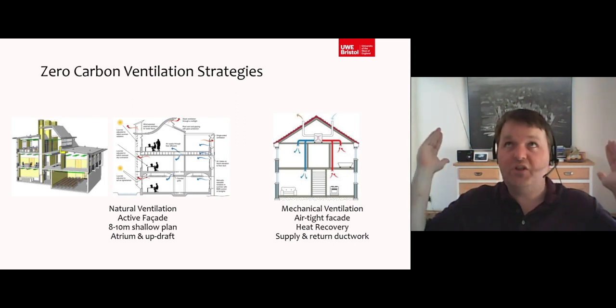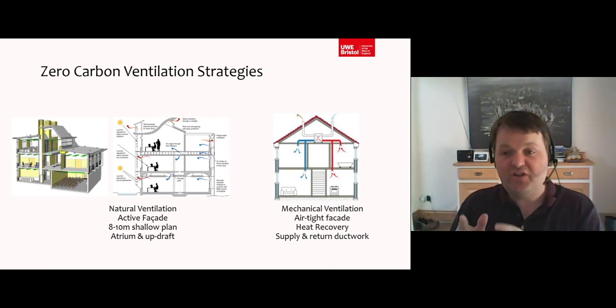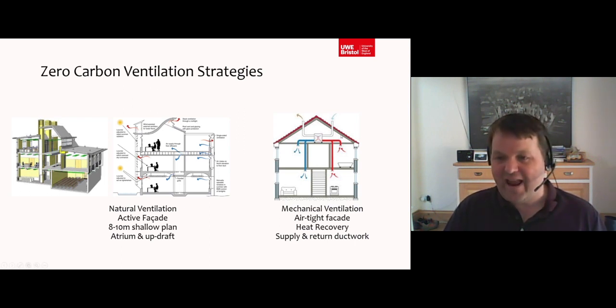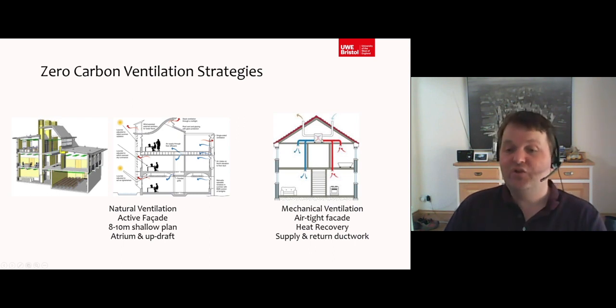You walk around London, you don't see openable windows in most buildings. They're all sealed up because they're using this strategy. And this one, it's much more invasive of the structure. You have to make your structure as airtight as possible. So you want to get this structure right down to be airtight in order to fit this technology called mechanical ventilation heat recovery. And it's denoted by the supply air, putting fresh air into the building. That fresh air then gets moved across the building into the staler spaces where there might be odors or moisture. That gets picked up and that gets taken back.